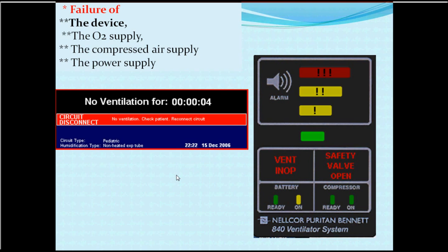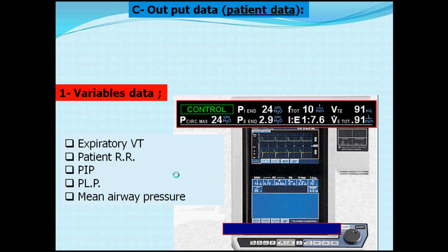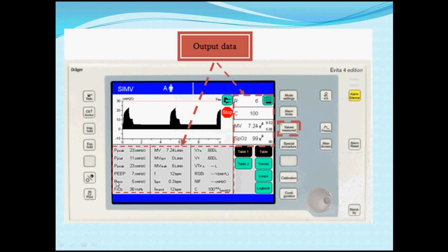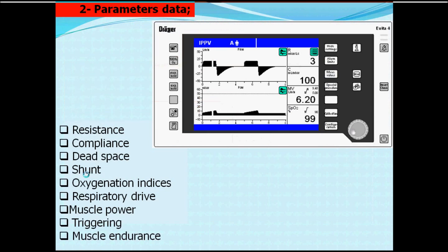The output data, an advanced technology feature, gives you numerical values or graphs about peak pressure, mean pressure, the I:E ratio, expired tidal volume, minute volume, and the ratio of inspiratory spontaneous to mandatory breathing. Additionally, it provides airway resistance (inspiratory and expiratory), compliance, minute volume, peak flow, maximal inspiratory force, and rapid shallow breathing index — a lot of data available from the output panel.